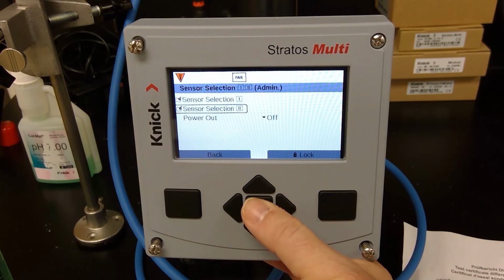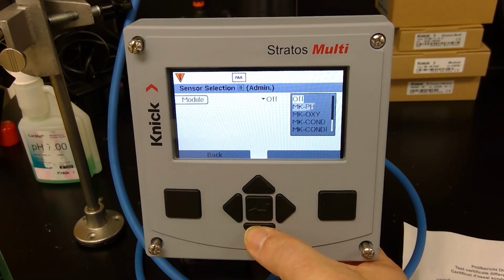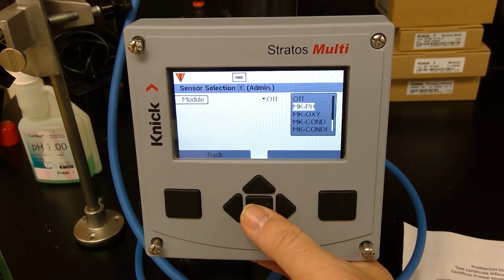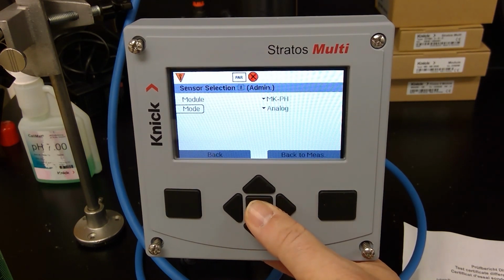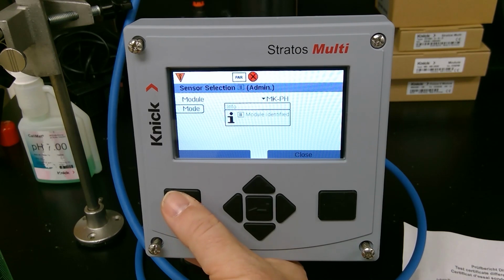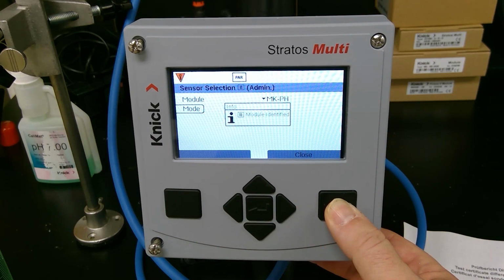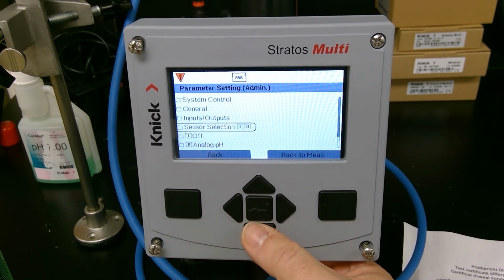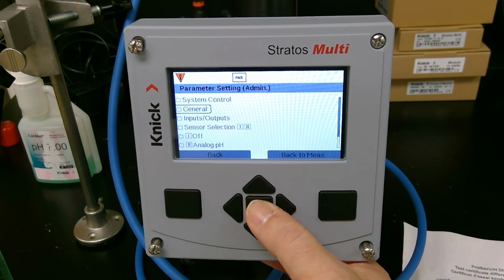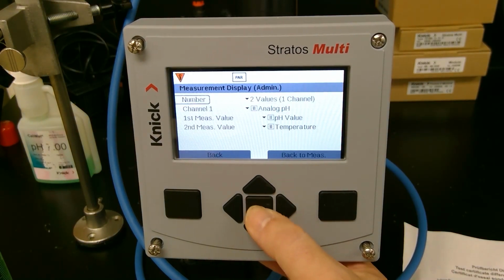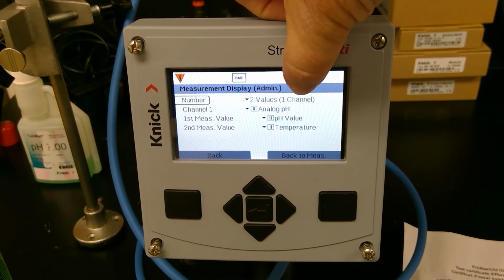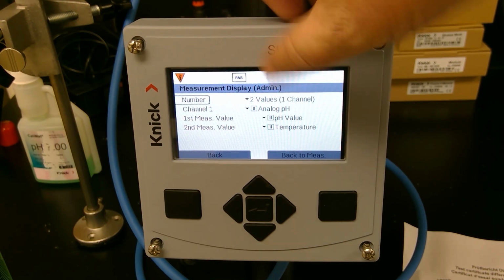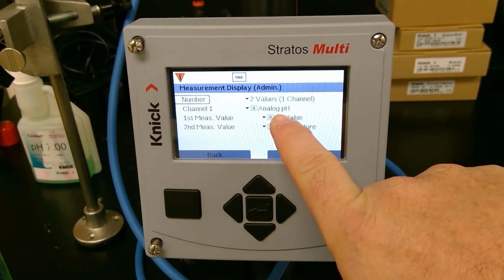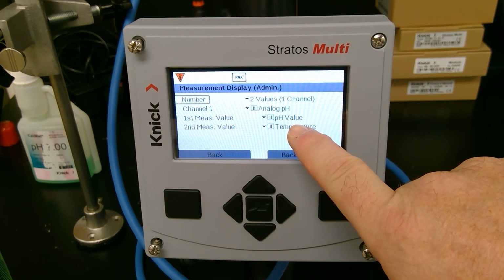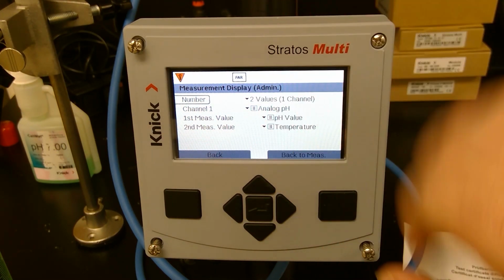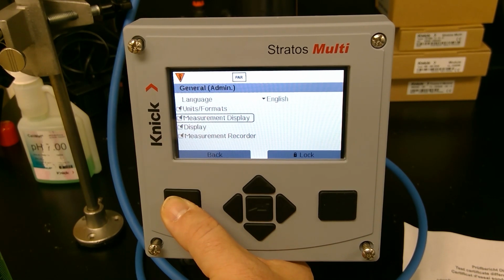That's perfect. I'll go into channel 2, and now I need to make sure I select the MK card, the MK-PH, and of course for analog, because this is an analog pH electrode. It's identifying the module. So then I come up to General, Measurement Display. Now this is already set up, but I want two values shown on my output channel 1, and I want it to be transmitting my input channel 2, which is analog pH. My first value is going to be the pH value, and my second is going to be the temperature value, and that's what's going to be shown on the display of the transmitter.